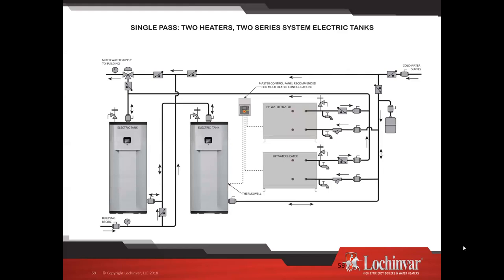hybrid system here. This is something that I less often recommend. This would be if we had two heat pump water heaters feeding electric tanks. Usually I would like it just for the last tank to have an element. The reason for that would be just as a boost or peak shaver, versus if the first tank in series starts dropping in temp, I wouldn't want that element kicking on and then kind of sandwiching the water.